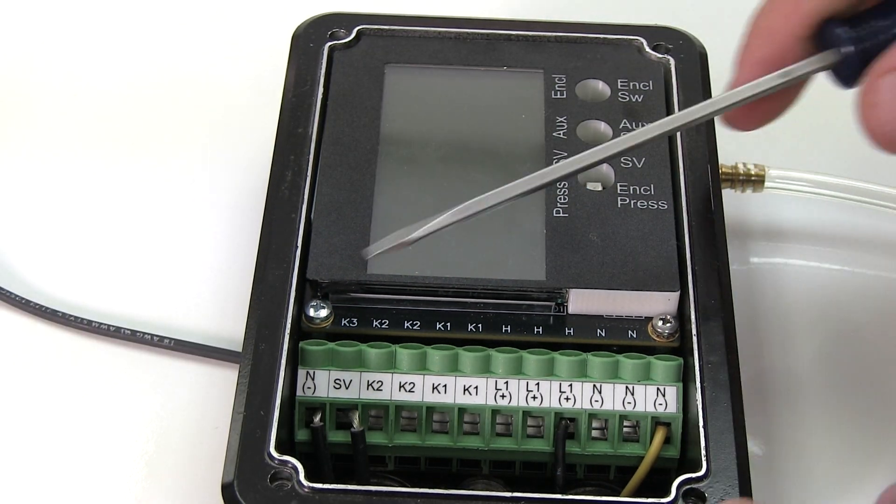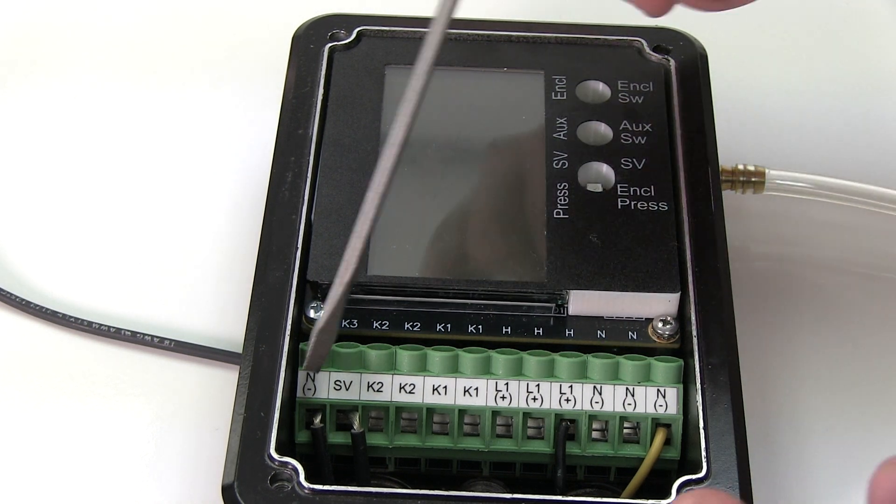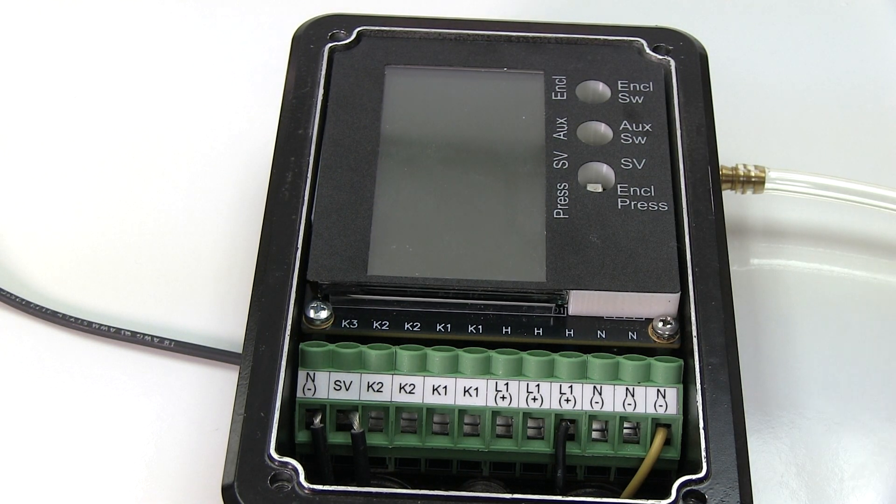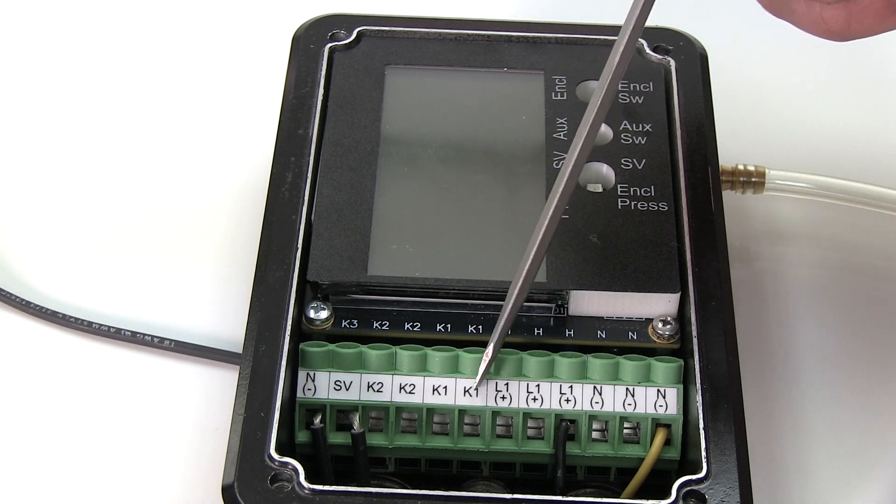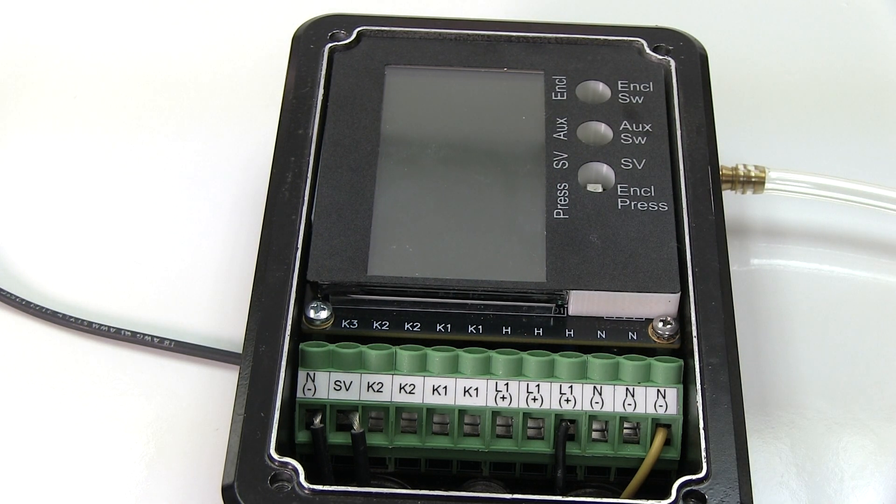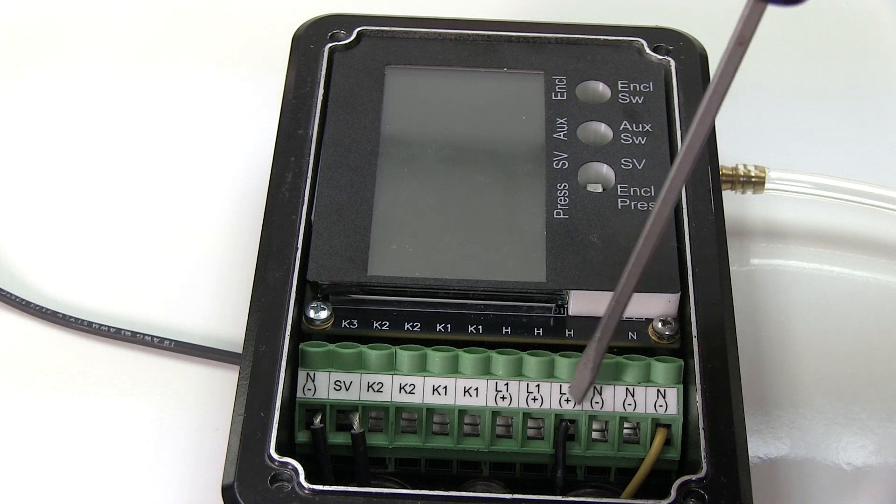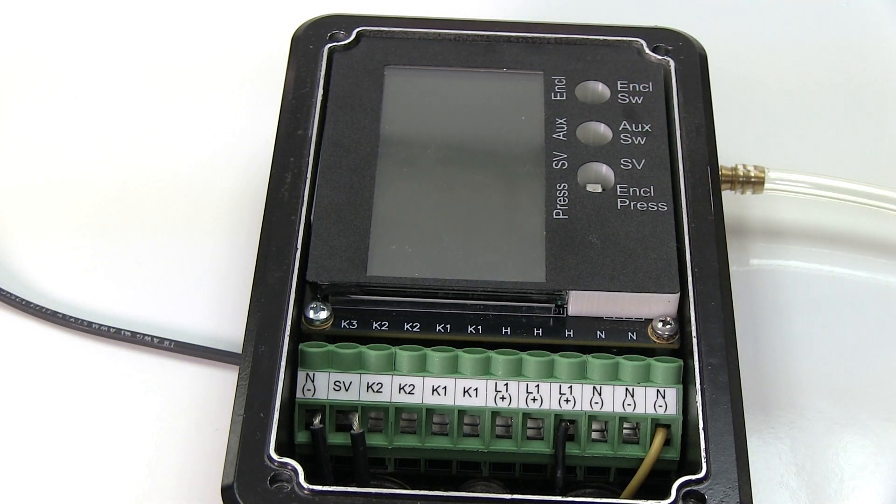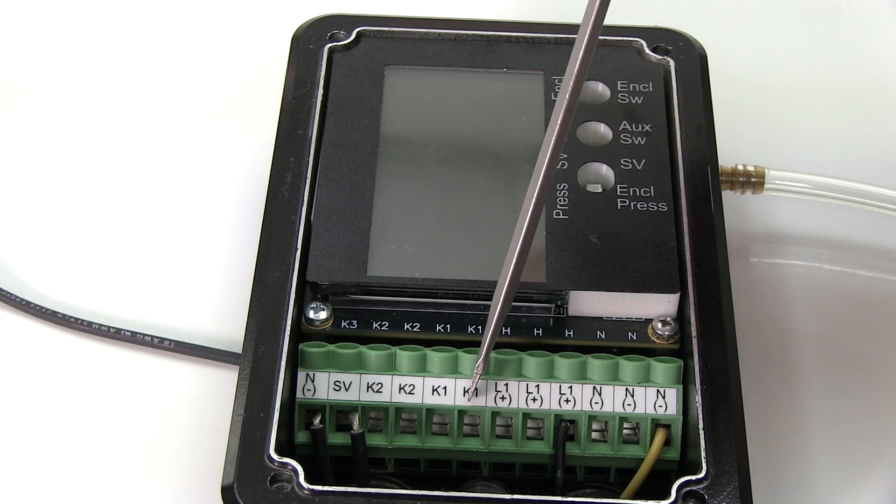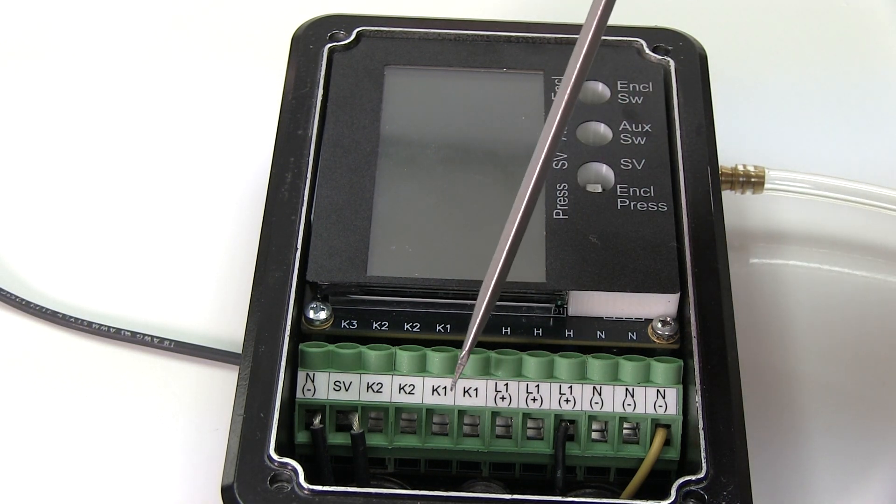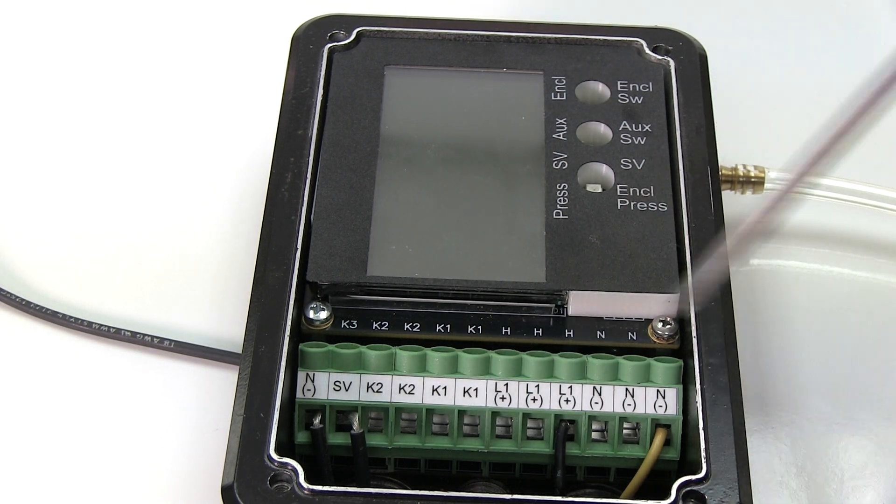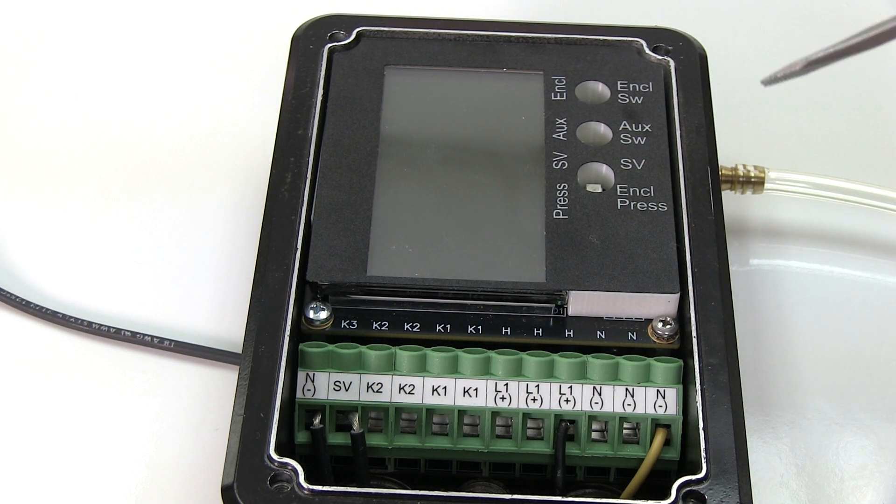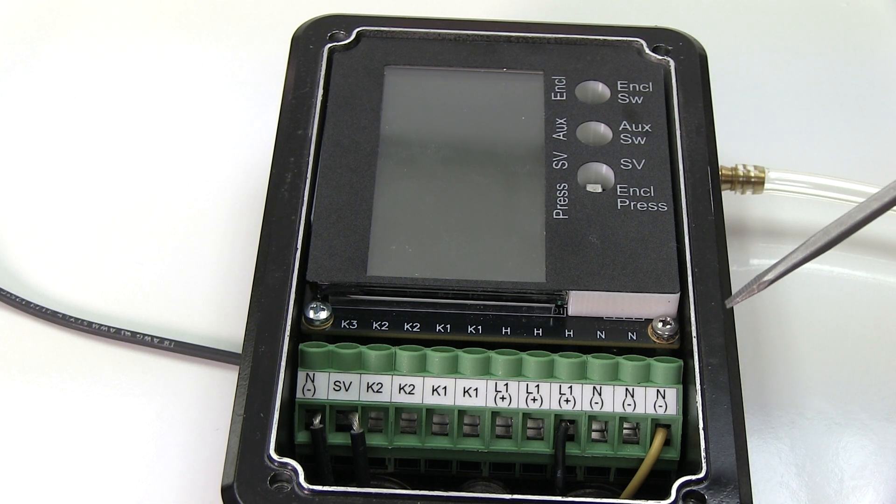Now that we have our solenoid valve wired up, the next thing we'll do depends on how you want to connect your K1 contacts and your K2 contacts. You can jump the power, whatever power you're bringing into the control unit. Just for this example, let's say it's 120 volts. I can jump 120 over to one of the K1 contacts and then take that and run it to my enclosure. So after it goes through its purging cycle, the K1 contact closes and will energize my enclosure.